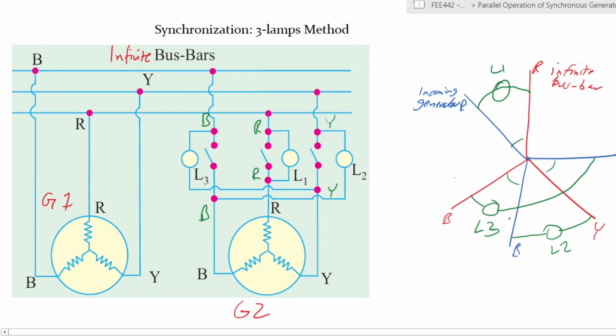Now, we said that the incoming generator is either slightly faster or slightly slower in terms of the phase angle than the infinite bus bar that it is going towards. So it will either be slightly faster or slightly slower. So it's tending to go backwards or to go forward, clockwise or anti-clockwise. In this case, let's just pick one, where we are moving forward, right? So it means that all these phases, the blue ones, that is the incoming generator, are all tending away from their counterparts within the infinite bus bar. So red in the incoming is faster than red in infinite. Blue in the incoming is faster than blue in infinite, and so on and so forth.